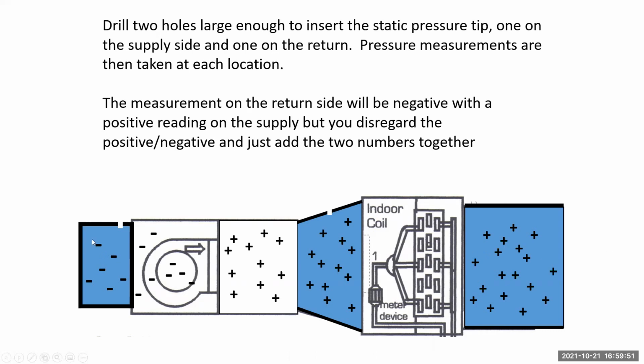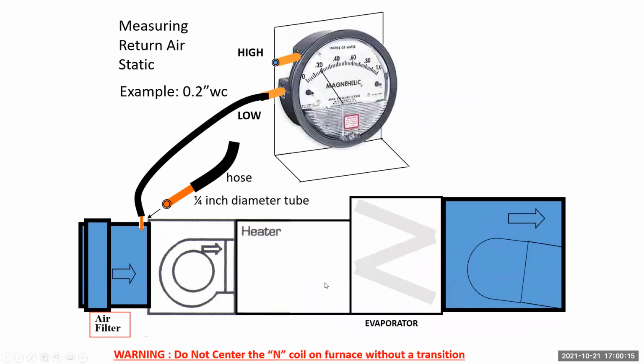This shows you again from left to right. Left, return into the blower, through the furnace, through the transition, through the evaporator, and out your supply. Get your holes large enough for your testing equipment. Don't drill them super big holes. Big enough for your tubes, your pitot tubes, and you'll be good to go. Manometers, Magnehelic gauges. There's a lot of older techs out there still have these bad boys. They're probably the most accurate testing equipment that's ever been manufactured for the HVAC world. They're bulky, take up space, they're very fragile.